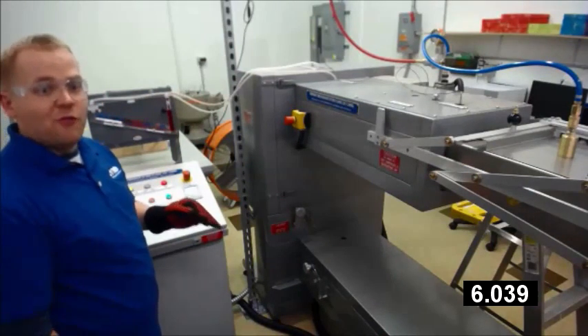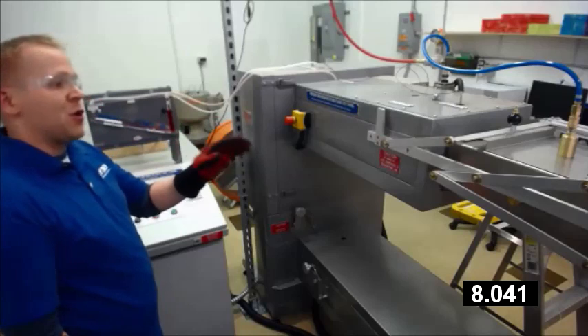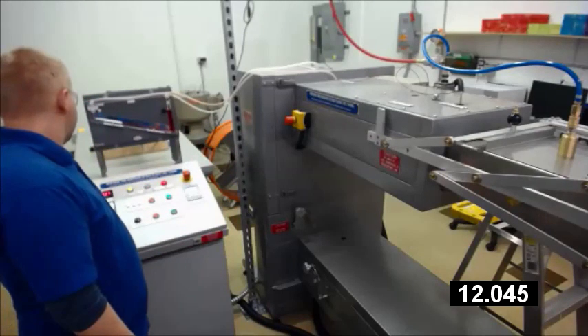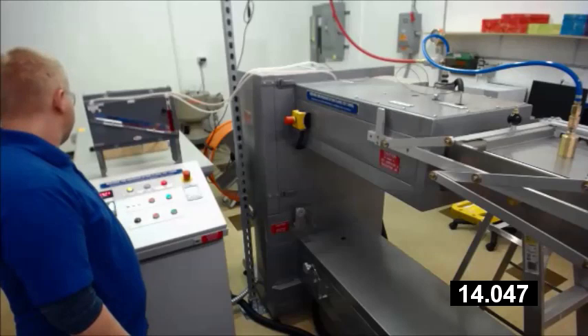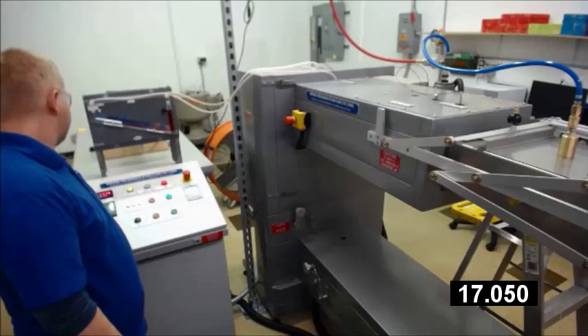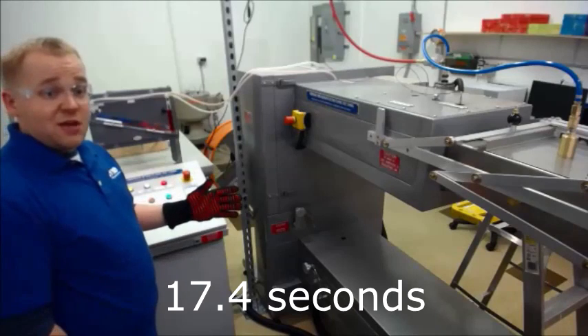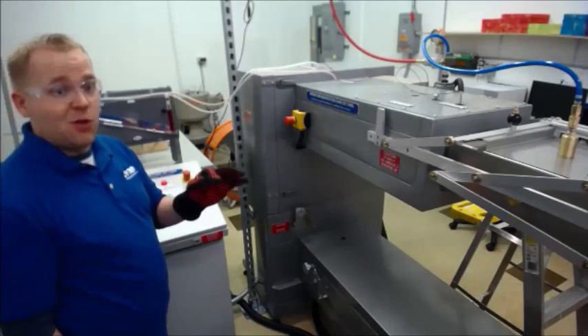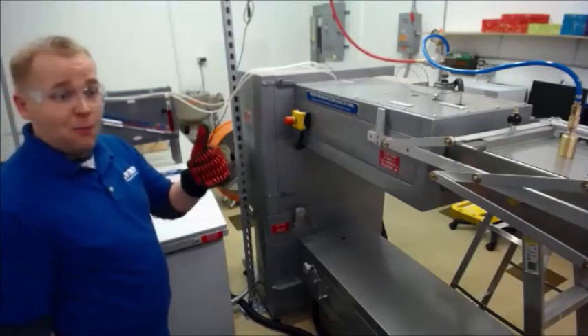Keep in mind that 12 to 14 seconds we were seeing with a brand new head. 17.4 seconds — that would fail. Even that small dust bunny was able to push that response time up past the requirement.